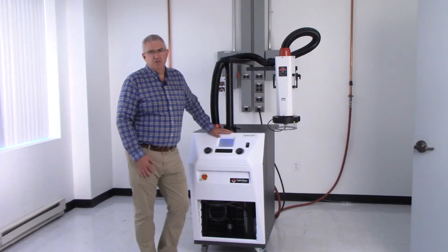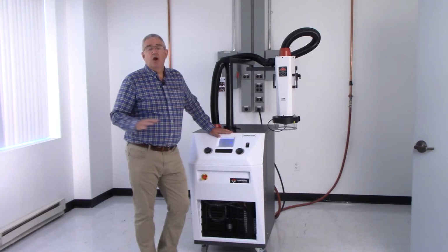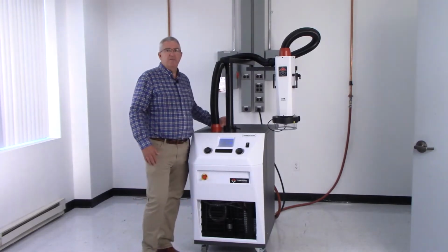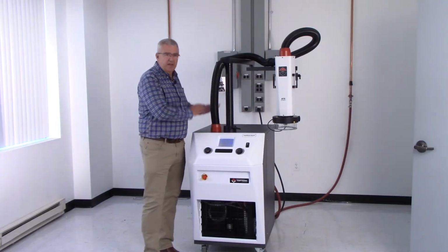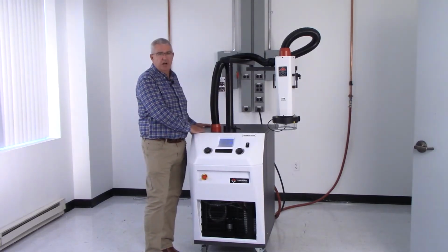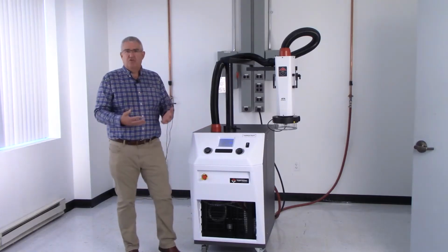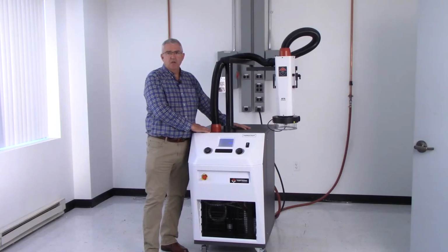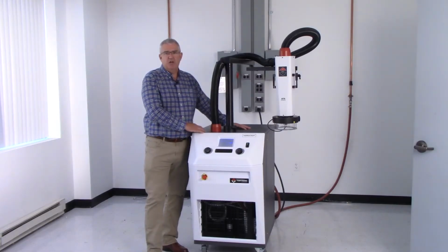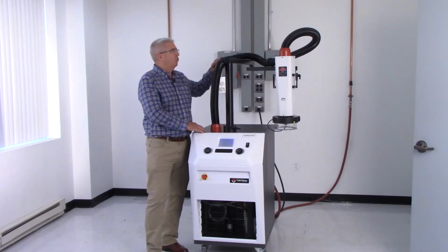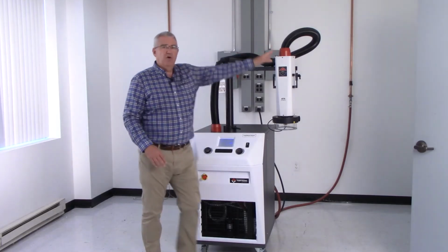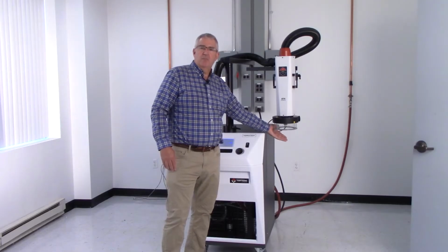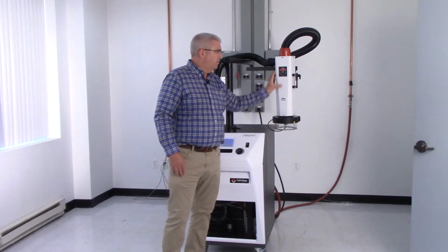The architecture of the system is very similar to all our other larger streams, in as much that in the rear of the system you get facilities air. The air then gets dried through an internal air dryer and then refrigerated. That cold air generated in the refrigeration system gets down to around -90 Celsius, then passes up through this hose to the thermal head, where the actual temperature of the air that comes out of the nozzle is then regulated by an internal heater.